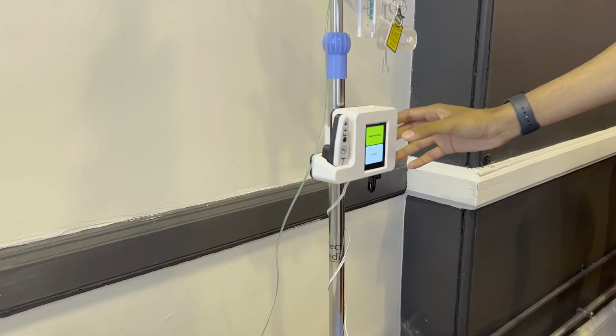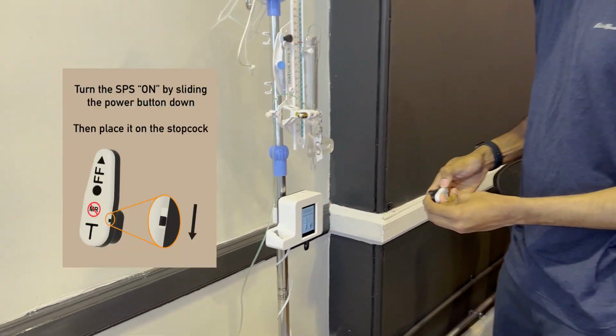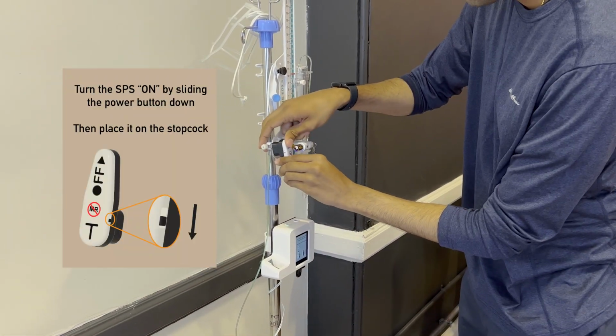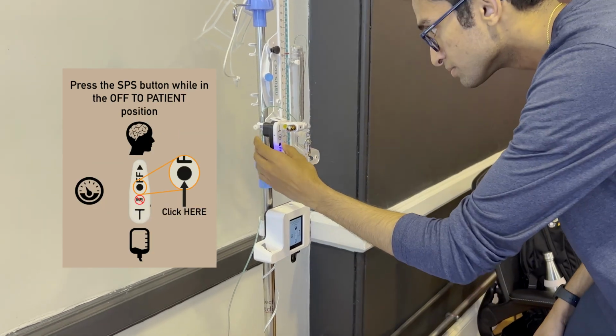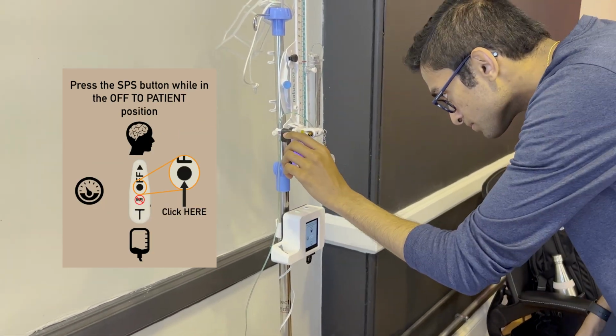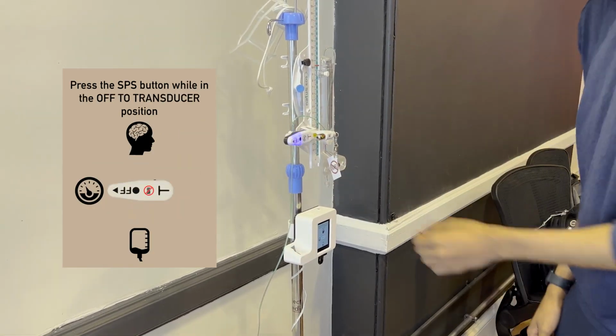Our solution includes the stopcock position sensor, or SPS, and our central hub. This allows clinicians to track stopcock position, light, sound, and temperature levels in the neuro-ICU, which enables the development of standard care protocols. We tried to make the operation of our device as simple as possible. On-screen instructions guide you through calibration, in this case, turning the device on, calibrating off to patient, off to transducer, and finally off to drain.